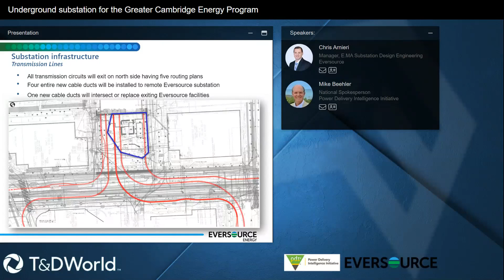Once we get the transmission lines into the station, as you've seen in the video before, the substation is very compact. The transmission lines are cross-linked polyethylene cables—some are multiple per phase, some single per phase, depending on the circuit. But there was no way we were going to route that through the substation successfully while leaving space for the other gear.